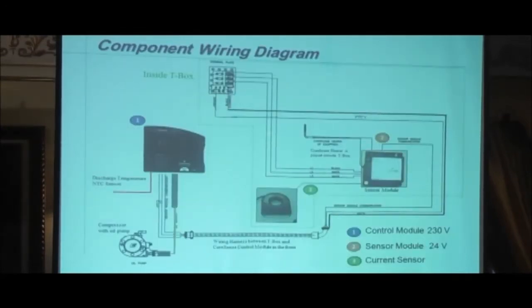This is the wiring schematic. The first thing I want to point out here is that all this wiring is done by Copeland in our factory. Alright. So you're going to receive a complete wired product. So we will wire up the oil pressure switch, we will wire up the sensor module, and then the PTC sensors on the motor. Okay. One important thing to remember is that this sensor module requires 24 volt. Okay.